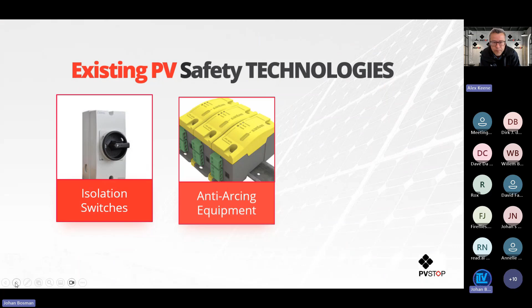So there are existing PV safety technologies, as we've already mentioned: isolation switches, anti-arcing equipment, rapid shutdown microinverters, DC optimizers. These are what we'd consider to be isolation and containment, being able to stop or manage the electrical supply and contain it to one part of the system where it can't hurt people. Anti-arcing basically recognizes and triggers a safety mechanism to avoid an electrical arc happening, but there are challenges around series and parallel arcing, so it's not a perfect system as it stands.